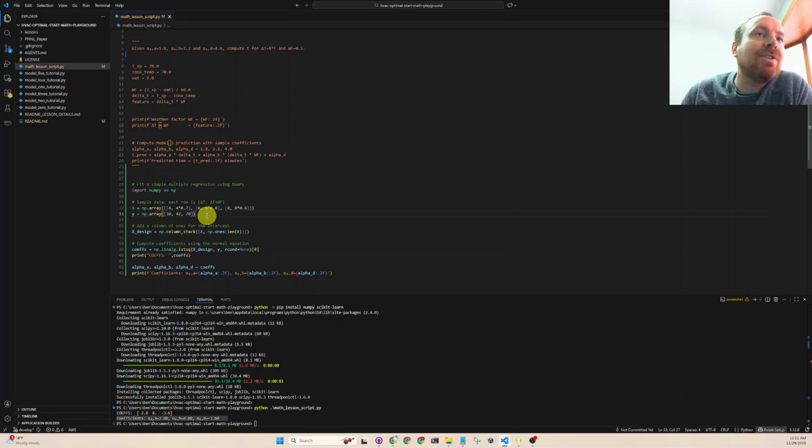In some of the other videos, there are computer science patterns that capture this, like when the optimal start algorithm runs, it records the temperature. Let's say it's 5 o'clock in the morning, the building's hot or cold, and it starts up at 6. That's our temperature delta: our zone temp compared to the occupied zone temp setpoint.